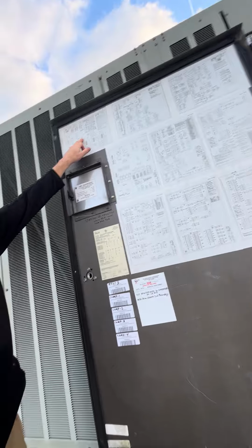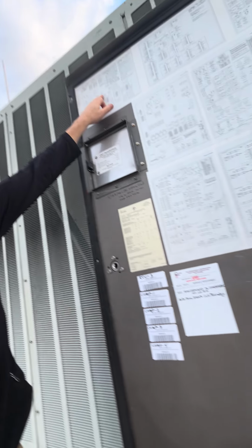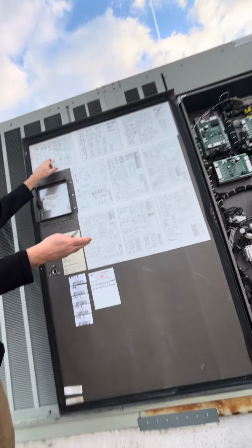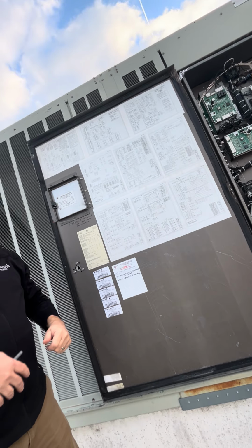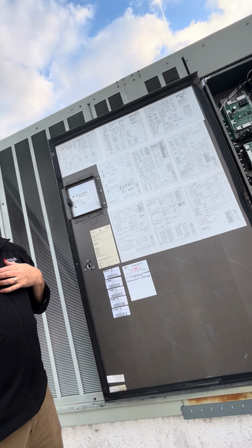And just to reiterate, you're saying you do not use that from the utility company to shut this off? We don't. You could. That's what it's kind of intended for. We kind of hijack it, and we use it as a cooling lockout. That's what we call it, mechanical cool lockout.